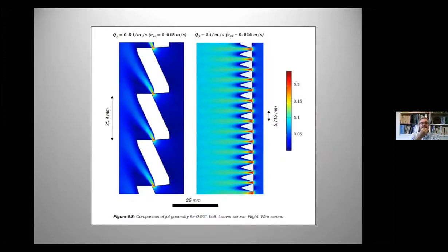And then lastly, this study here shows a high-powered computer model that was run by a company called Amphos. We at Roscoe Moss were trying to research some of these head loss components through the screen, and further we're going to take this study to learn more about the dynamics going on inside the screen and the well itself. What kind of head losses are being introduced based on screen type and screen geometry? As a manufacturer, this is important for us to know, because if we can make modifications to the way we provide these screens to certain users, we can help reduce overall head losses.